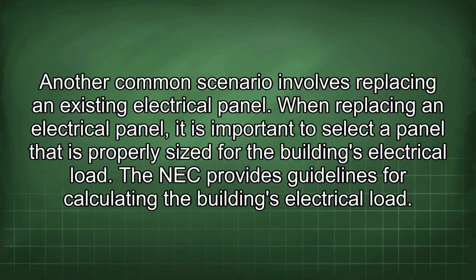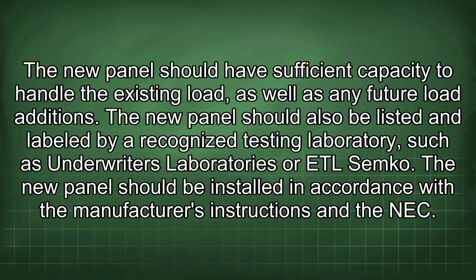Another common scenario involves replacing an existing electrical panel. When replacing an electrical panel, it is important to select a panel that is properly sized for the building's electrical load. The NEC provides guidelines for calculating the building's electrical load. The new panel should have sufficient capacity to handle the existing load, as well as any future load additions. The new panel should also be listed and labeled by a recognized testing laboratory, such as Underwriters Laboratories or ETL Semko. The new panel should be installed in accordance with the manufacturer's instructions and the NEC.